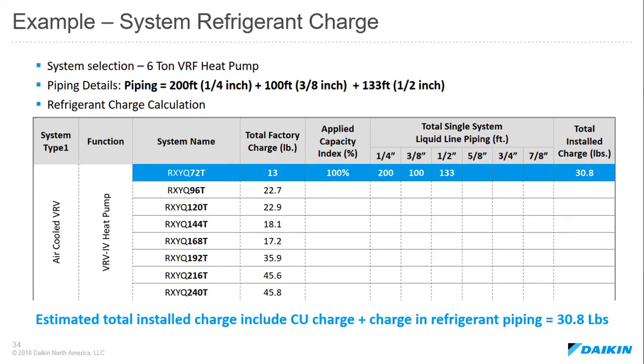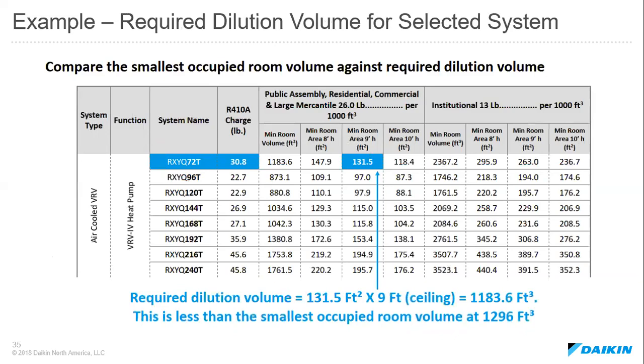We'll actually go to a special chart that will tell us, number one, what is the factory charge in the outdoor unit. In this case, that's 13 pounds, looking at the highlighted blue line. And then we'll look at the lengths of all of our piping runs. In this case, we had 200 feet altogether of 1/4-inch pipe. We had 100 feet of 3/8 inch pipe, and 133 feet of 1/2 inch refrigerant piping. So adding that all together, looking at all the refrigerant in the piping and the outdoor unit, the sum is 30.8 pounds of refrigerant.